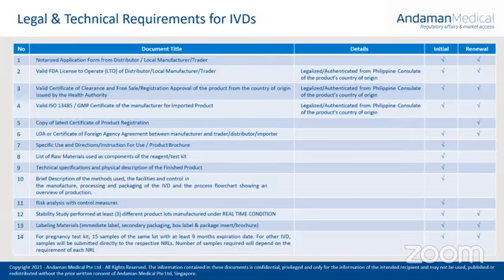That for foreign or imported medical devices, the ISO or the QMS document of the legal manufacturer and the physical manufacturer shall also be submitted. So either ISO 13485 or GMP certificate. Copy of the latest certificate of product registration or CPR. This is only applicable for renewals if you are doing renewals for IVDs. LOA or certificate of foreign agency agreement between the manufacturer and trader, distributor, or importer. So LOA or your agreement with your foreign supplier or agreement with another manufacturer here in the Philippines. This is also one of the requirements for IVDs.